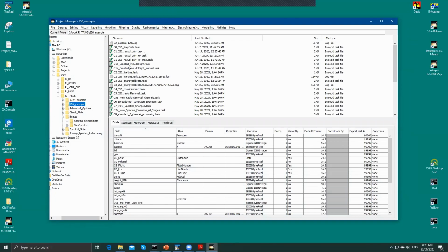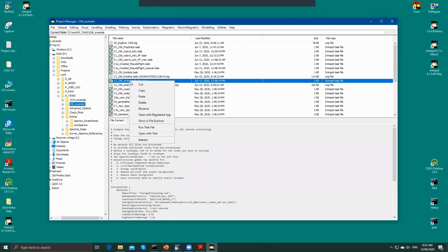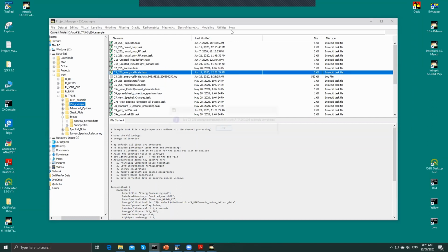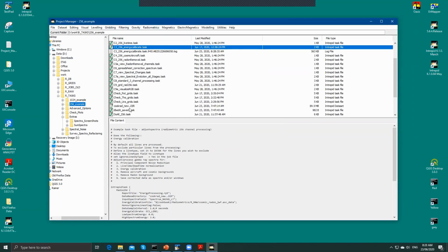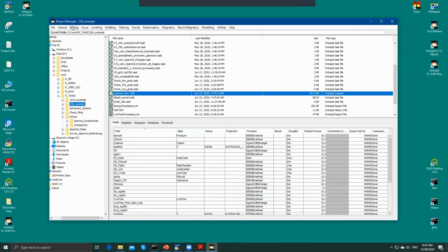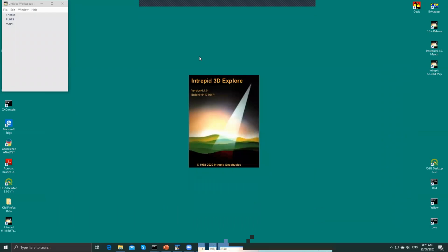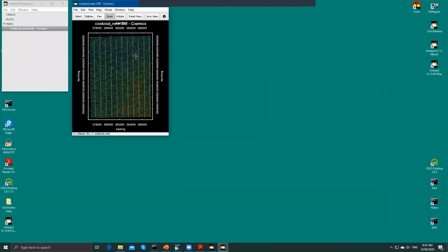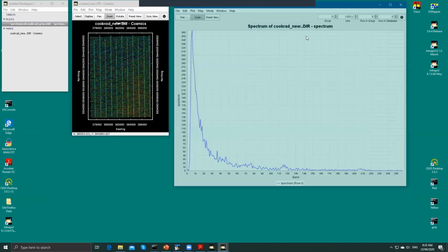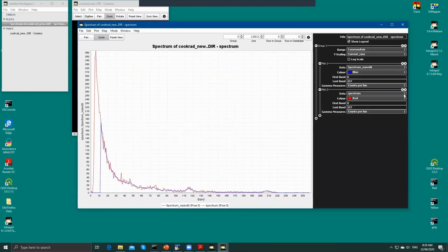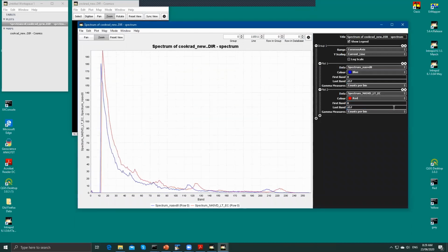Yeah, maybe we just run that again. And straight from the task file, C3 256 energy calibrate task file, just run task file. Let's see whether maybe I hit the wrong button somewhere. So this one is done. Then let's have a look again. Maybe I did something wrong in the GUI.